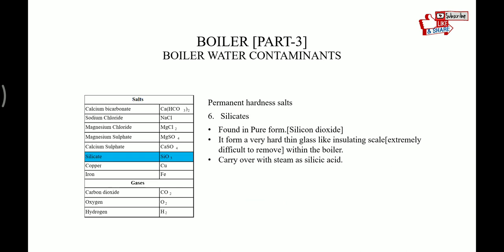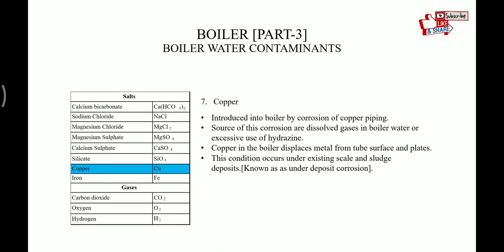Silicate is found in the form of silicon dioxide. It forms a very hard, thin, glass-like insulating scale which is extremely difficult to remove within the boiler. It is carried over with the steam as silicic acid. Copper is not a salt but is present as a contaminant. It is introduced in the boiler by corrosion of copper piping. Sources of this corrosion are dissolved gases in the boiler water or excessive use of hydrazine. Copper in the boiler displaces metal from the tube surface and plates, a condition known as under-deposit corrosion.